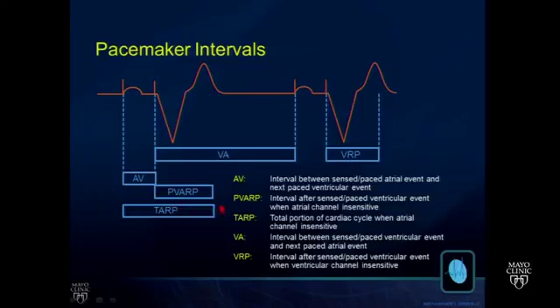There are 5 normal electrocardiographic expressions of normal DDD permanent pacemaker function. Let's review what those are. If you have a DDD pacemaker and there is no interacting native rhythm, so it's just the pacemaker, you're going to see what's called AV sequential pacing. AV, VA, AV, VA, indefinitely. If there's no native event, you have the expiration of the AV interval followed by the initiation of the VA interval. When it completes, you pace the atrium and reinitiate the AV interval, and so on.